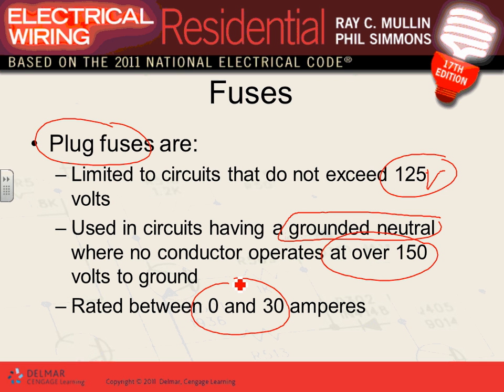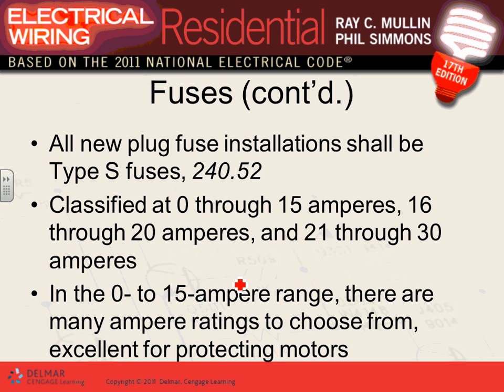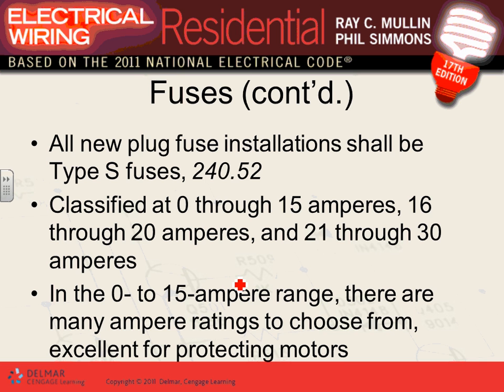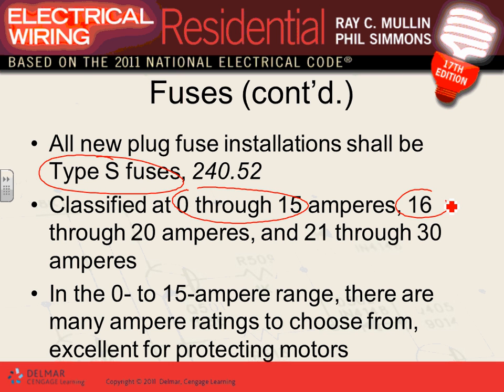All plug fuses have to have Type S fuses. Type S fuses classify you between 0–15 amps, 16–20 amps, and 21–30 amps. If you go with number 14 conductor, you're in the 0–15 category; number 12 goes with 16–20; number 10 goes with 21–30.